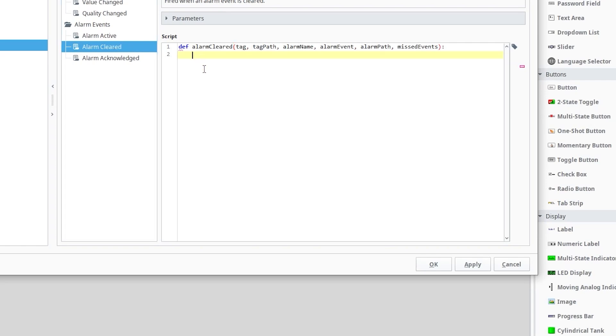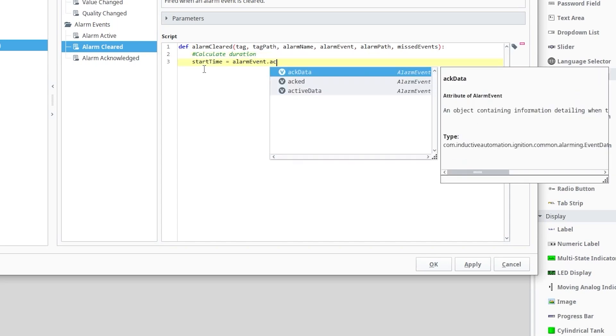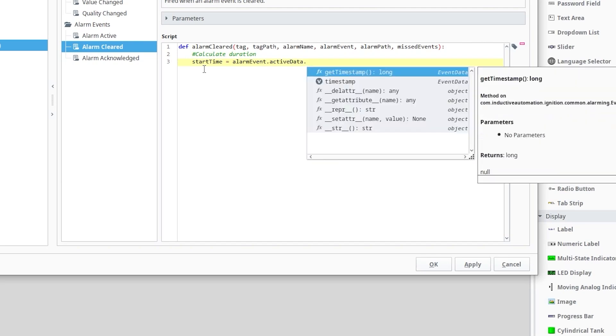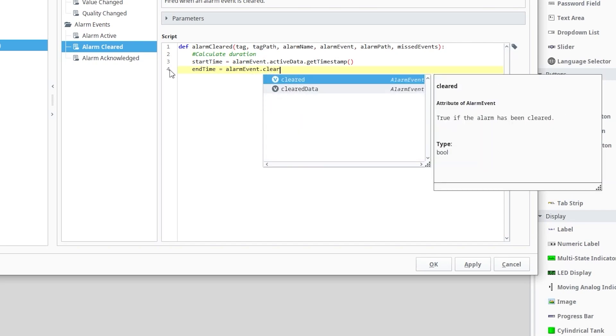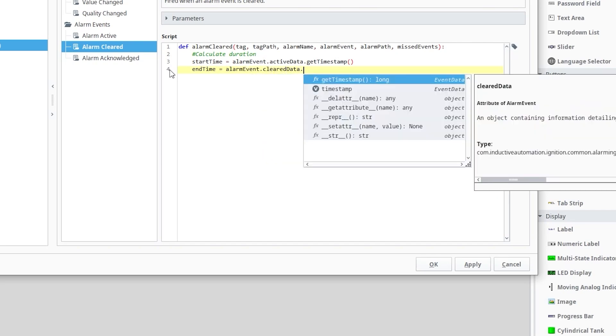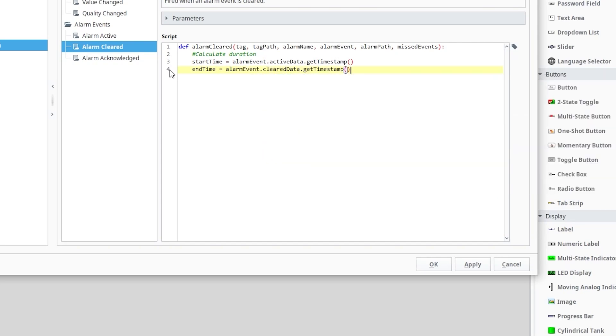Let's calculate the total duration of our alarm. To start, I'll create a startTime variable and set this to alarmEvent.ActiveData.GetTimeStamp to give us the time our alarm went active. Similarly, I'll need an endTime variable and set this to alarmEvent.ClearedData.GetTimeStamp to give us the time the alarm cleared. We'll calculate our duration by subtracting our startTime from our endTime.